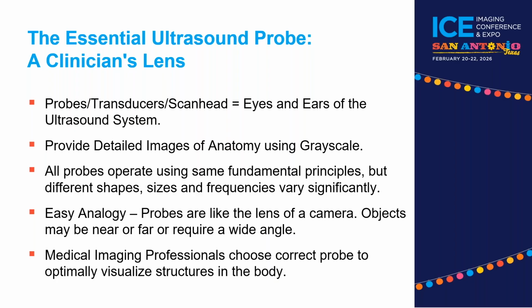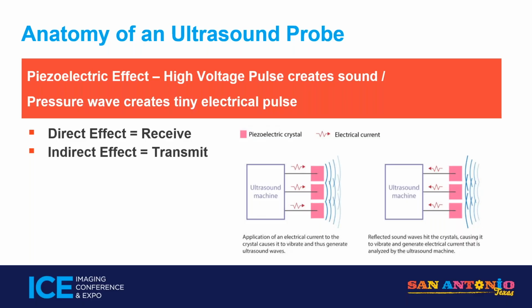So one of the things that we have to understand is how probes work. We call it the piezoelectric effect. Basically, quartz crystals they discovered back in the old days, back in Madame Curie and all that, had this unique characteristic about it. If you hooked up high voltage to the quartz, it would vibrate, sending out sound waves into the atmosphere. And the other unusual portion of it is if you hit it with a pressure wave, the same material would generate tiny electrical pulses. So it had two kind of unique properties about it.